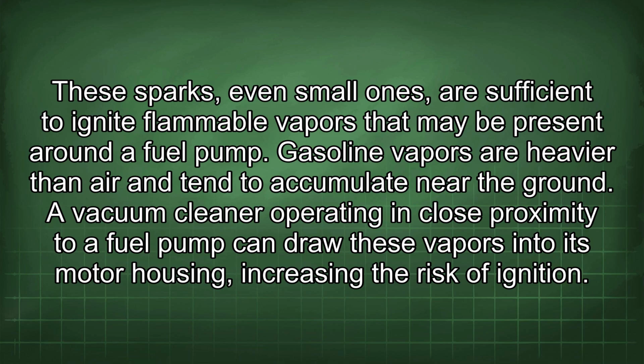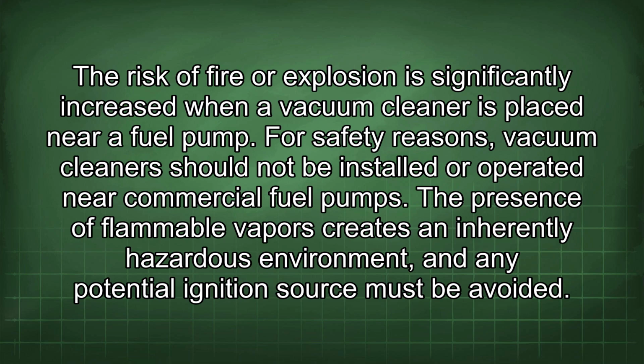Gasoline vapors are heavier than air and tend to accumulate near the ground. A vacuum cleaner operating in close proximity to a fuel pump can draw these vapors into its motor housing, increasing the risk of ignition. The risk of fire or explosion is significantly increased when a vacuum cleaner is placed near a fuel pump. For safety reasons, vacuum cleaners should not be installed or operated near commercial fuel pumps.